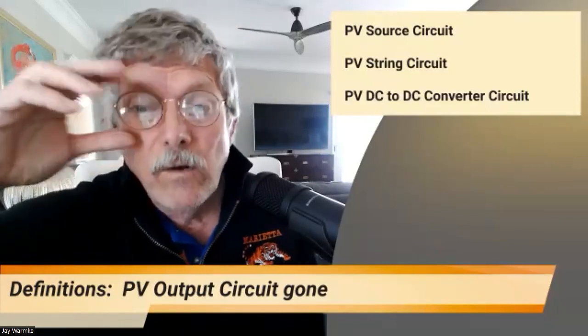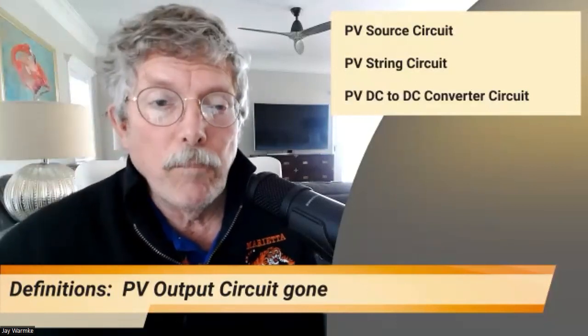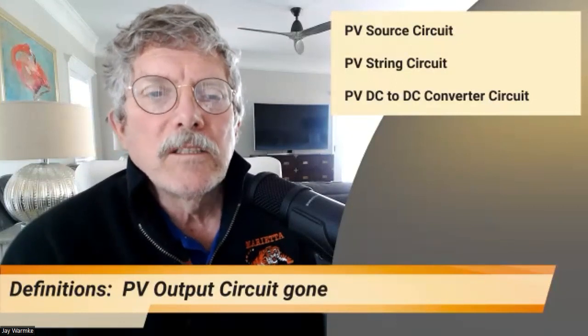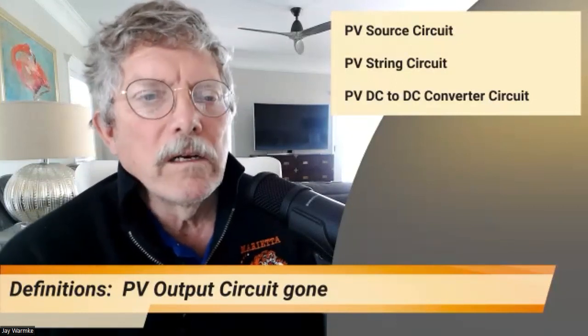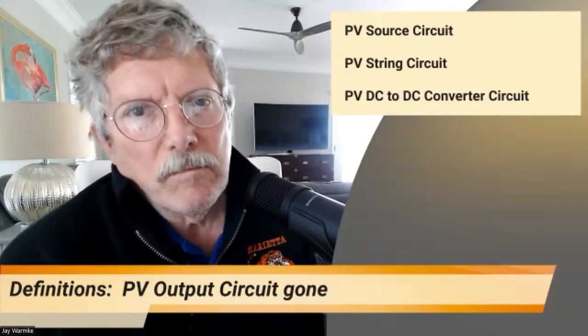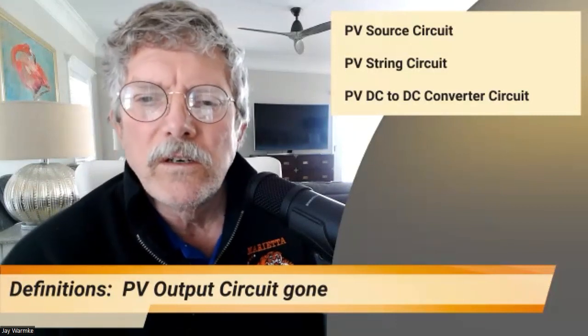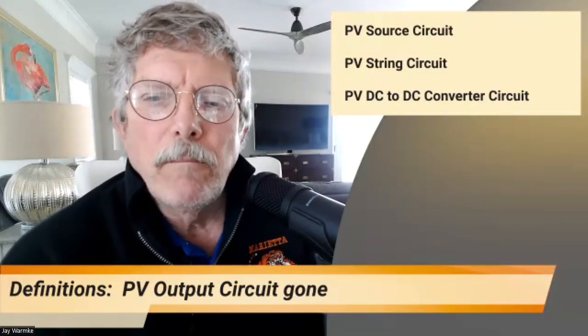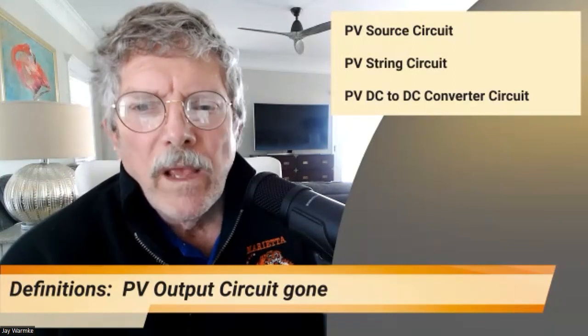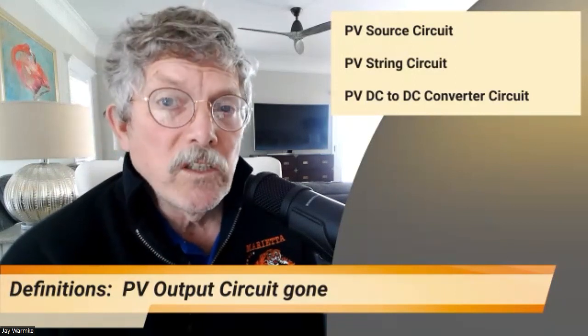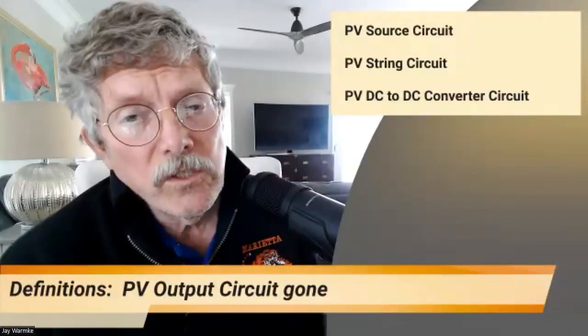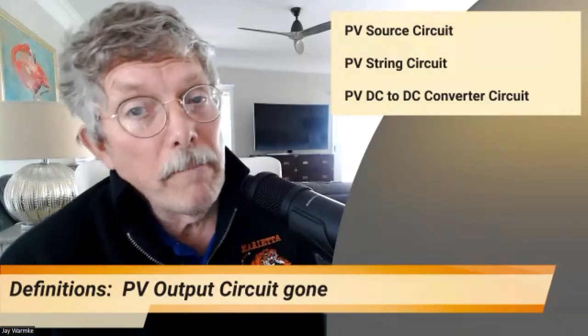Well, they've done away with the PV output circuit. That terminology is no longer considered acceptable as far as the code is concerned. They've talked now about PV source circuits and PV string circuits, and the PV source circuit might be a PV string circuit, or it might not be.